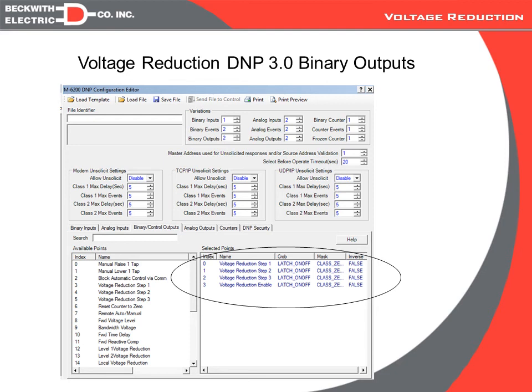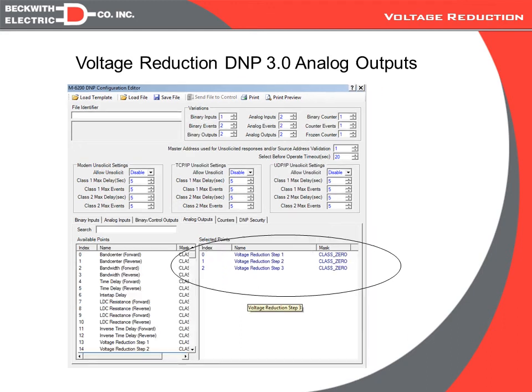So for instance, if I wanted to do like we saw before and start with a level 2 and then go to a level 1, I can send a latch on to the level 2. Then I would say after 30 seconds or so, giving the regulator time to settle down into its new voltage, then I could follow that with a latch on level 1. That will automatically bring me out of 2 and into 1. And then when I wanted to leave altogether, I would have to do a latch off on level 1. So that is how the digital outputs or the binary outputs work.